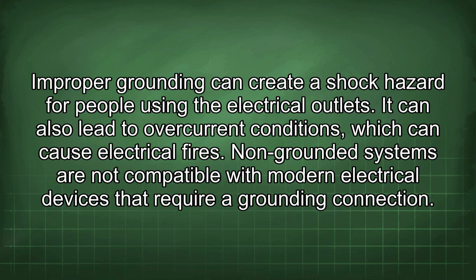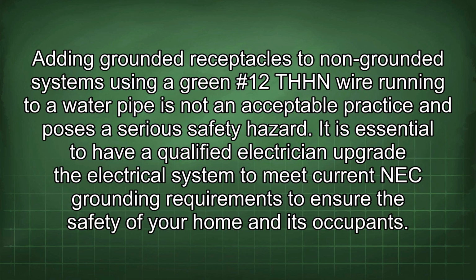Non-grounded systems are not compatible with modern electrical devices that require a grounding connection. Adding grounded receptacles to non-grounded systems using a green #12 THHN wire running to a water pipe is not an acceptable practice and poses a serious safety hazard. It is essential to have a qualified electrician upgrade the electrical system to meet current NEC grounding requirements to ensure the safety of your home and its occupants.